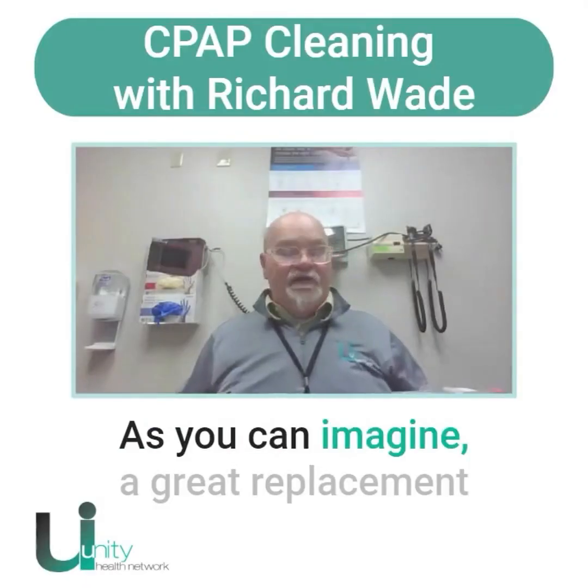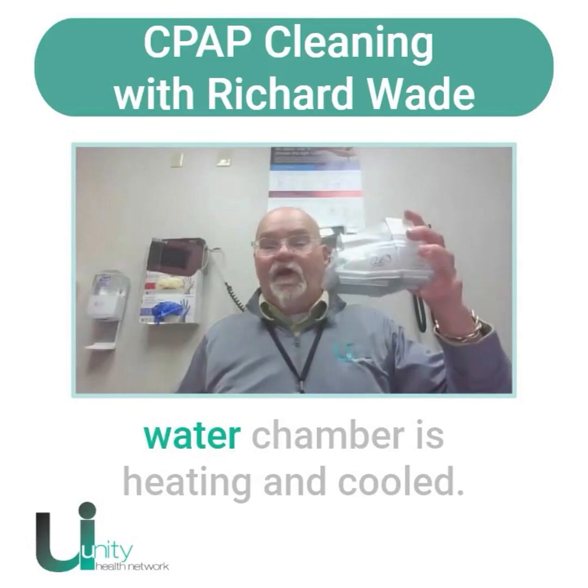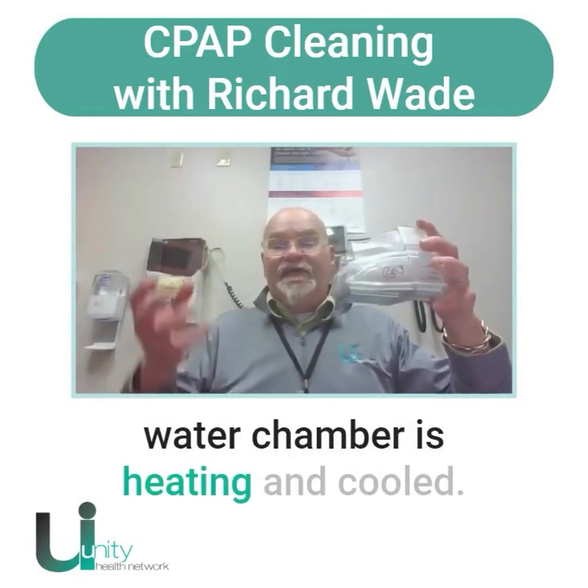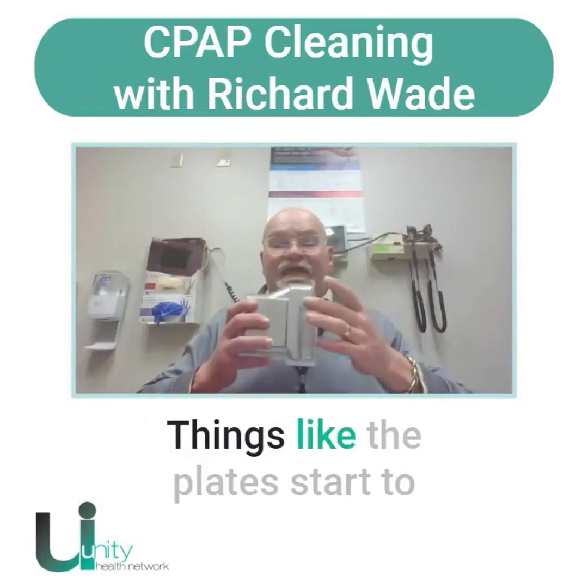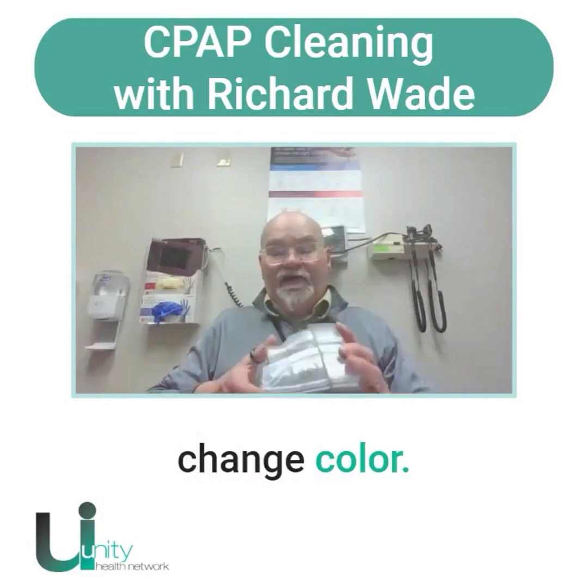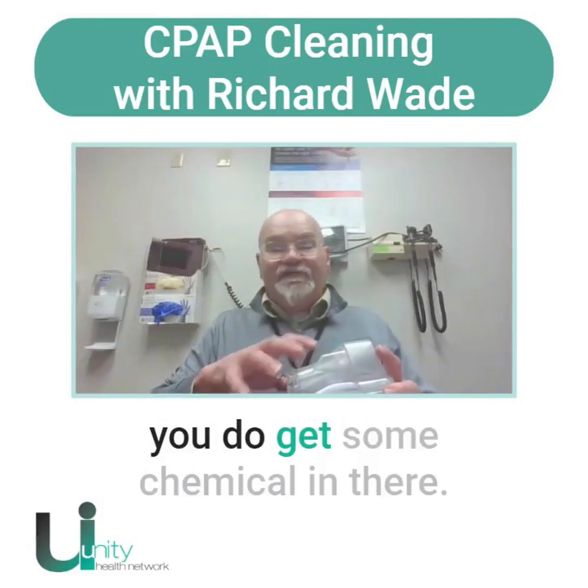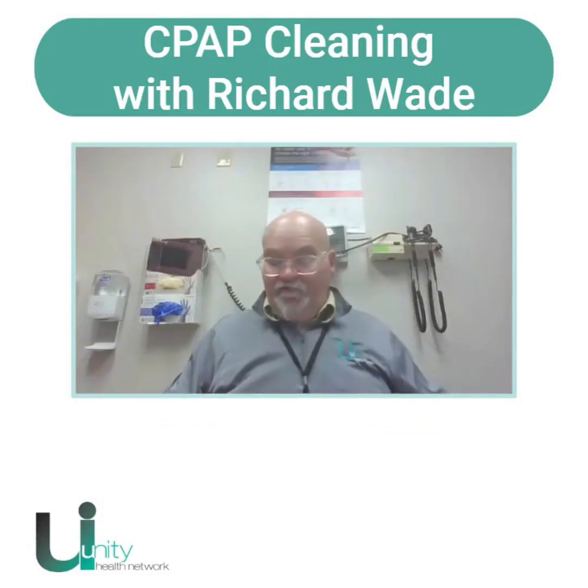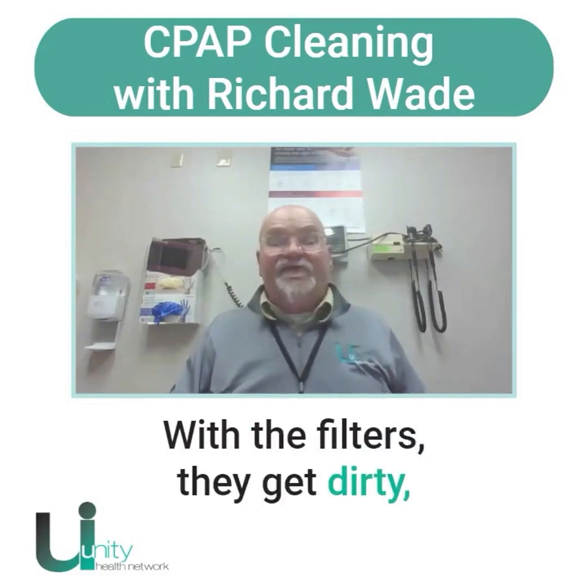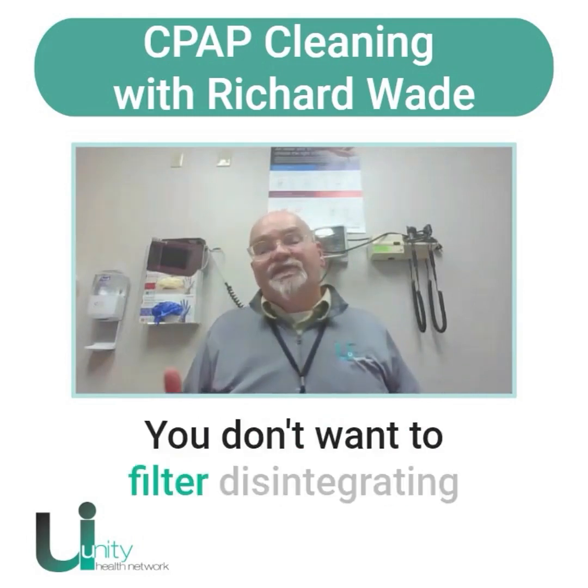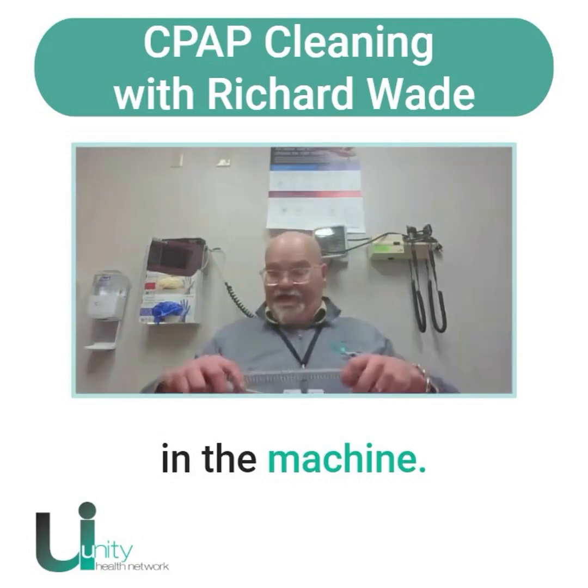As you can imagine, there's a great replacement schedule because this water chamber is heated and cooled. Things like the plates start to change color, and even with distilled water you do get some chemical buildup in there. With the filters, they get dirty and break down. You don't want a filter disintegrating in the machine.